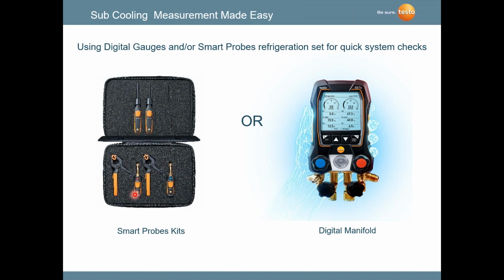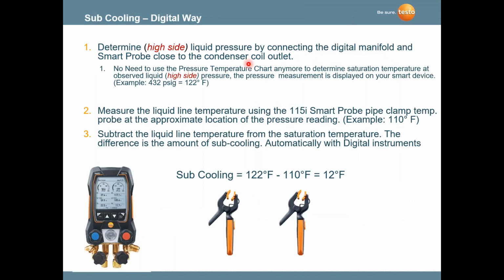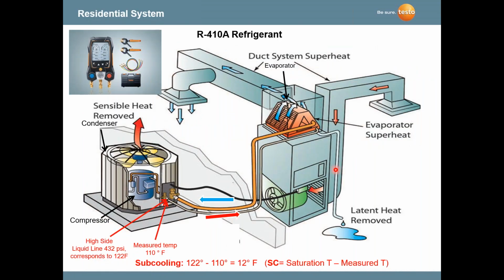Again, with digital instruments, you'll see two sides of a digital instrument here. One side is the low side, one side is the high side. You'll see two temperature probes here, one for low, one for high. Two pressure probes here, one for low, one for high. And then you have a kit that shows your relative humidity sensors. Same thing. You're looking at high side liquid pressure, getting the readings automatically, seeing the 432 psi, which is converted to 122 degrees Fahrenheit saturation temperature. The probe on the high side is measuring 110 degrees Fahrenheit. So we're automatically getting and calculating the subcooling of 12 degrees Fahrenheit. Quicker, faster, and more accurate.